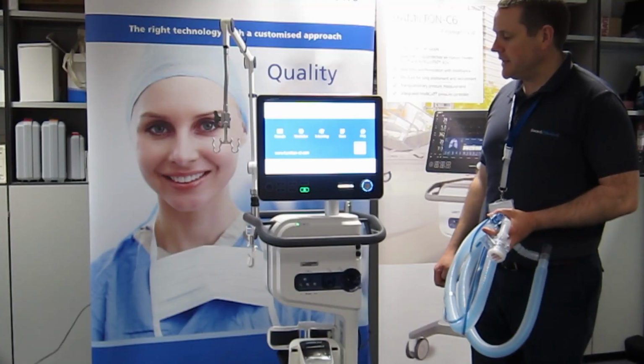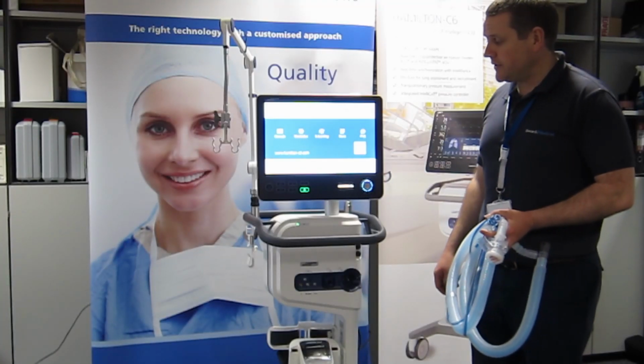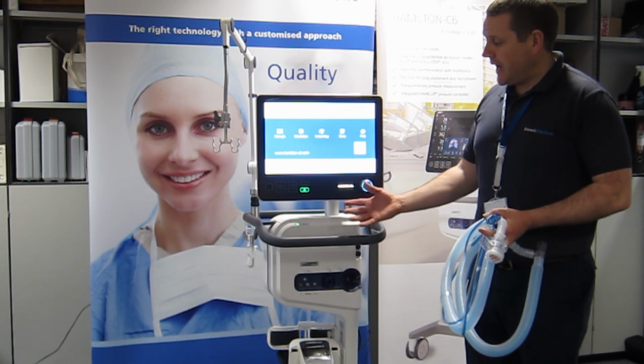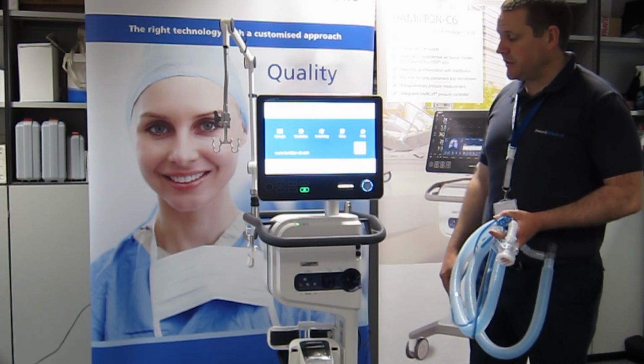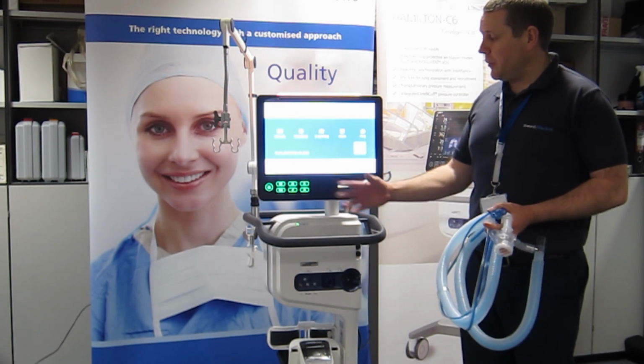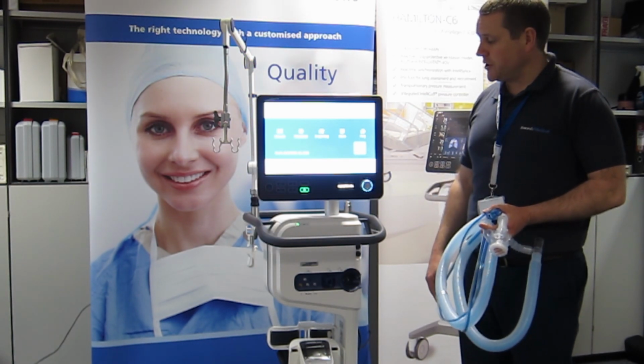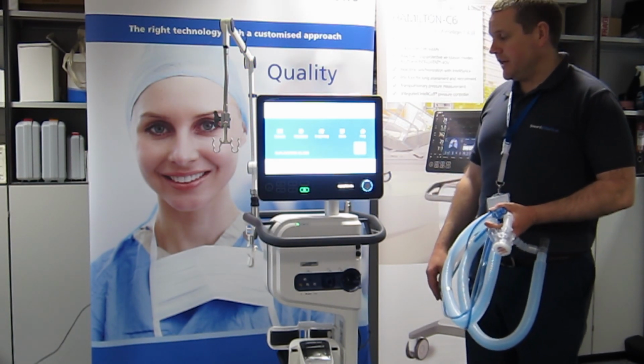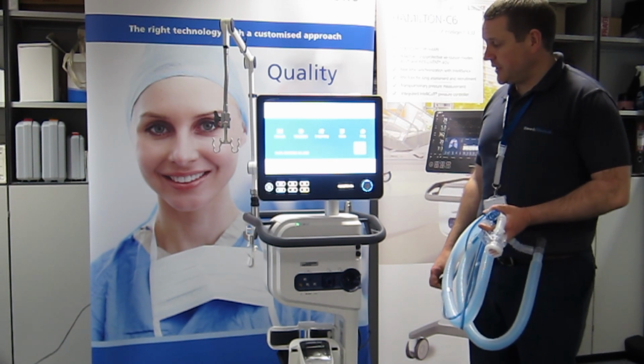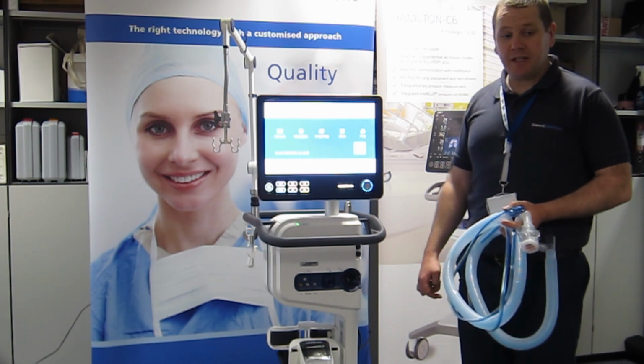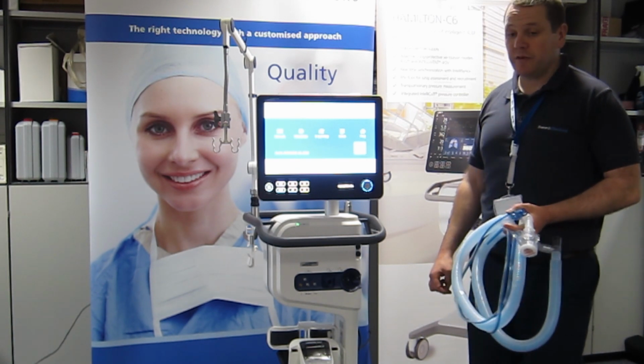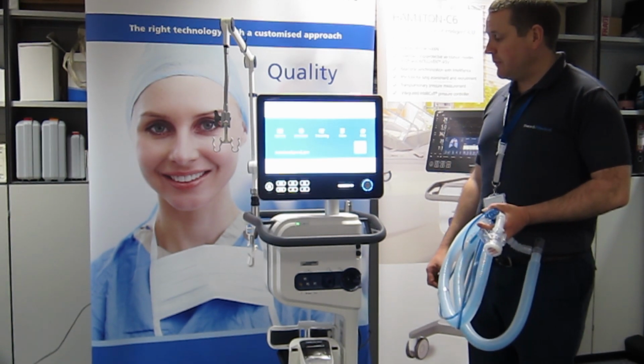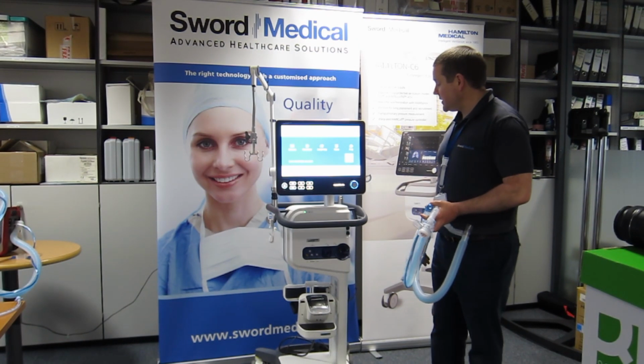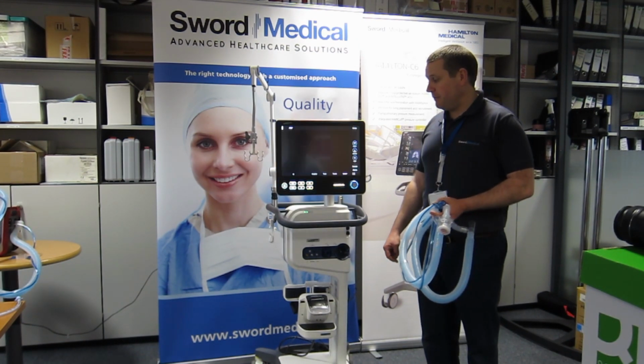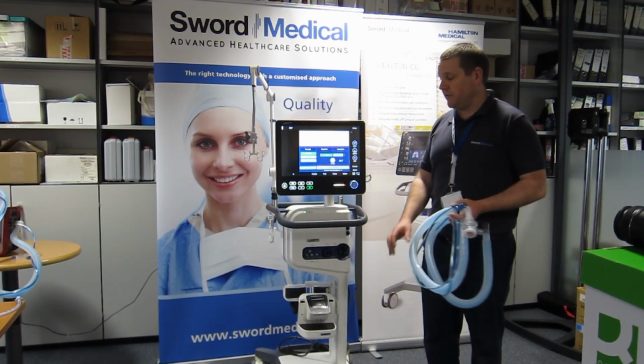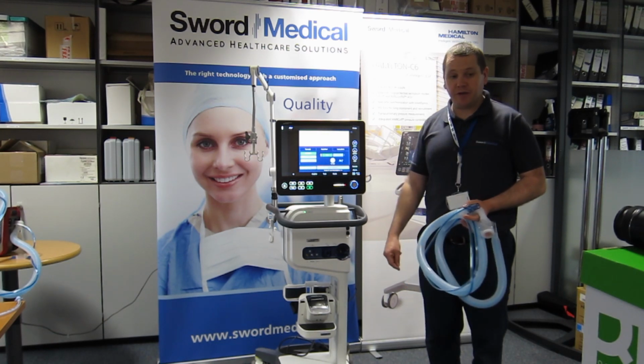So we would recommend that the ventilator is turned off when it's not in use, so whoever comes to it has to turn it on. It only takes about 20 or 30 seconds to turn on, but you know that when it's turned on, it's in perfect working order. Also, there are 2 batteries on board this particular ventilator, both 90 minutes each, so you have 3 hours from a full charge of battery power. So we'd recommend that the ventilator is left plugged in at all times. So whoever comes and wants to move the ventilator, when they unplug, they know they have 3 hours from that point.